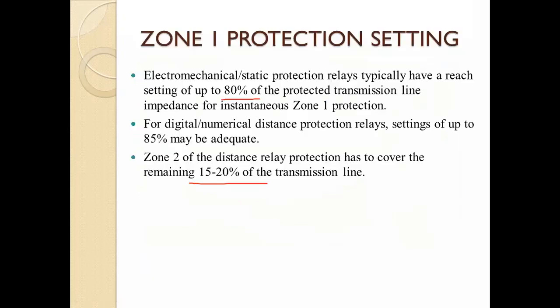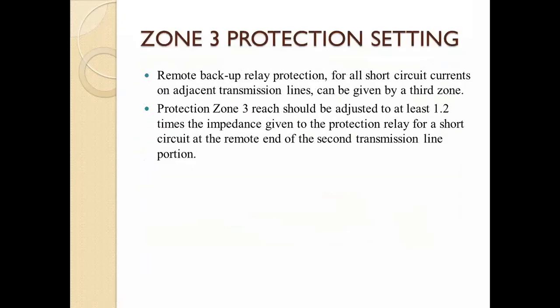So here in zone 3, it is a remote backup relay protection for all short circuit currents on adjacent transmission lines. It is given as backup protection when severe short circuit faults happen there.